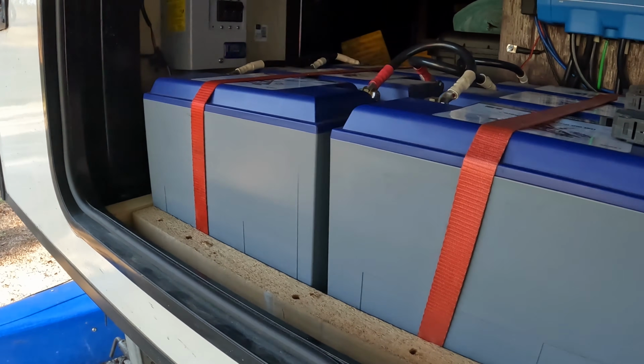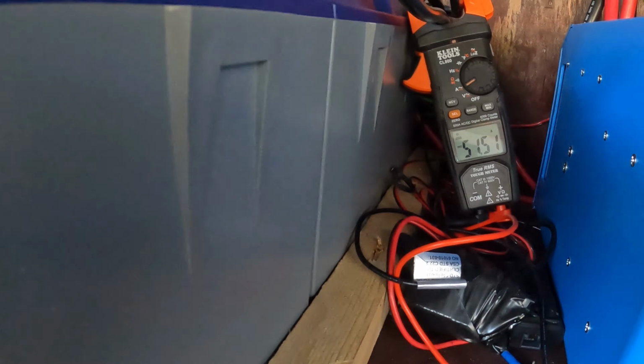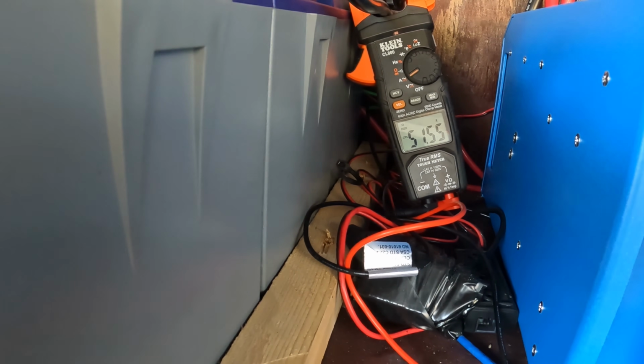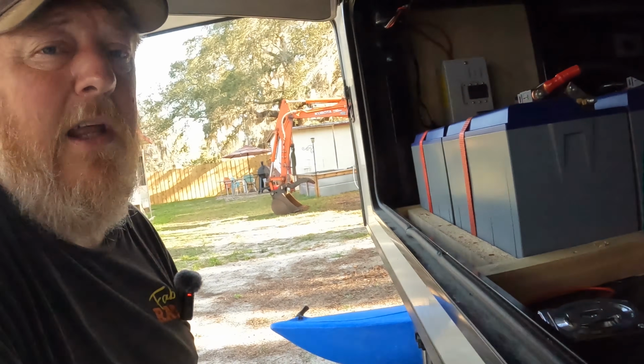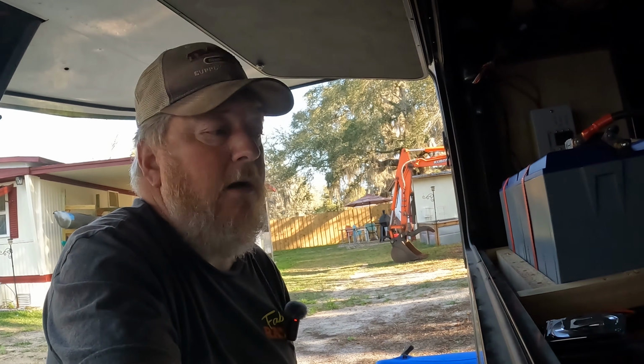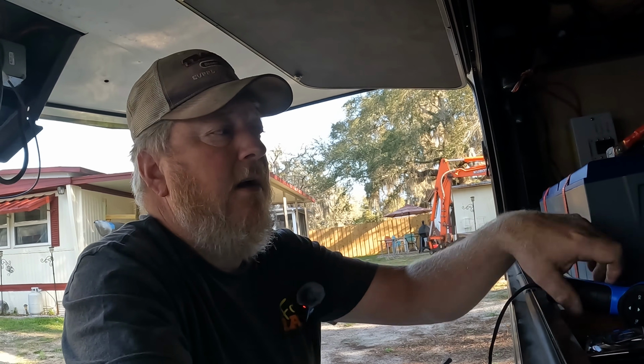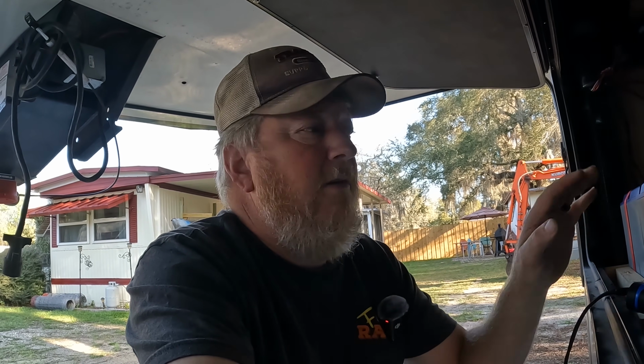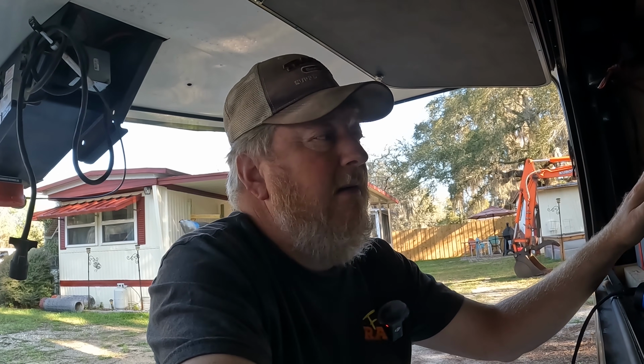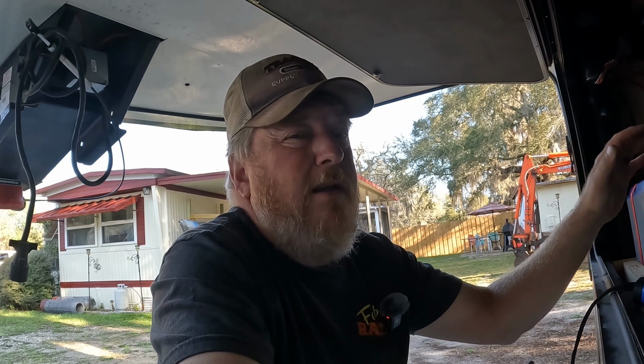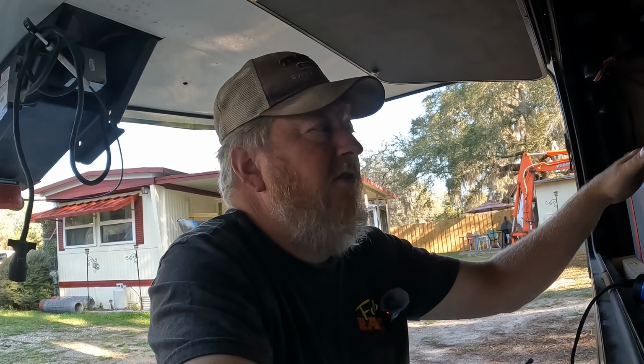As I said, that's running on 2 batteries at 50 amps for 10 minutes now, and they're already in the 90-something degree range. I have a feeling, and it's cool here, probably 60 degrees Fahrenheit, that if this door was closed on this baggage bay and we were in a 40 degree C ambient instead, we'd probably be in the 110 to 120 degree range already on this battery in 10 minutes.